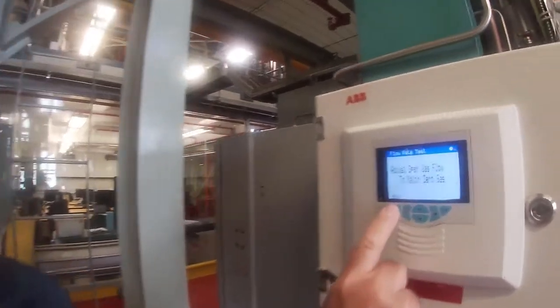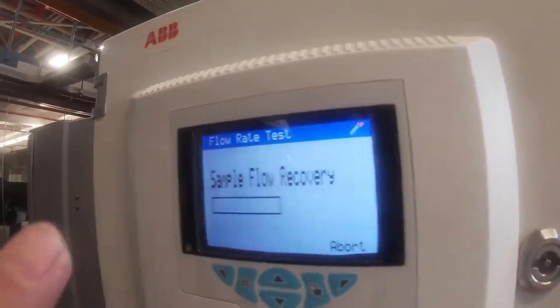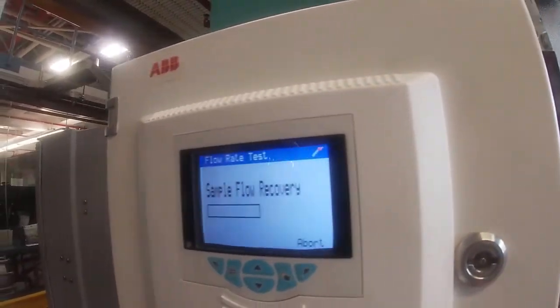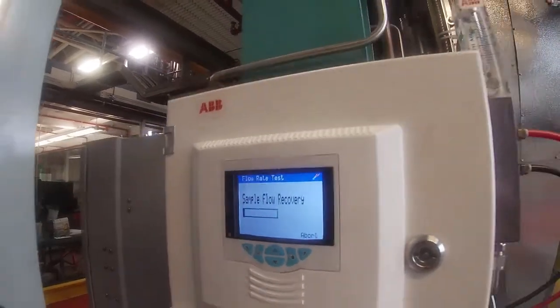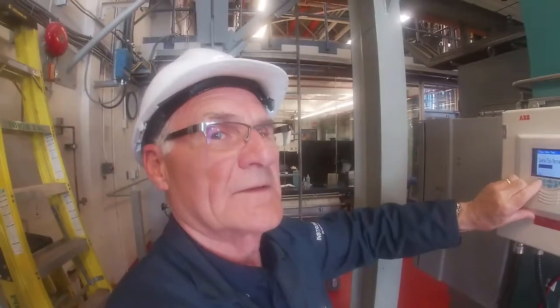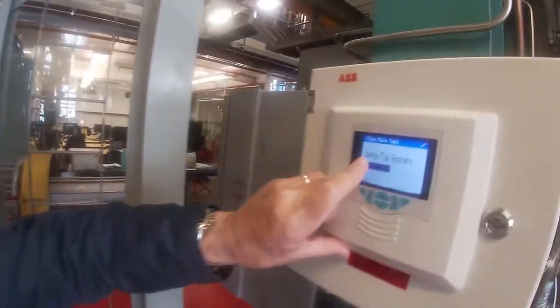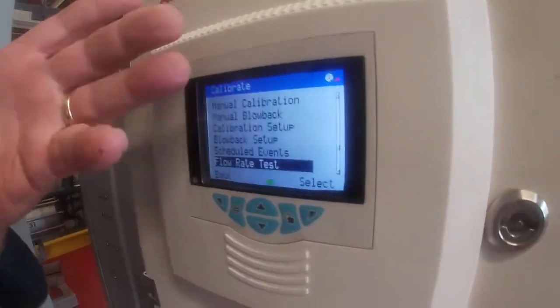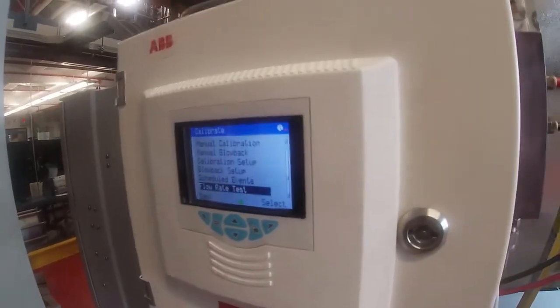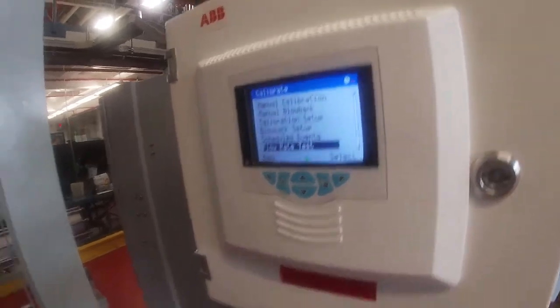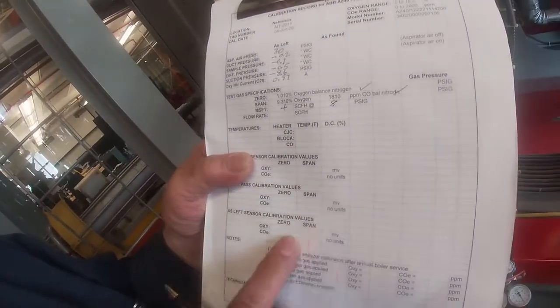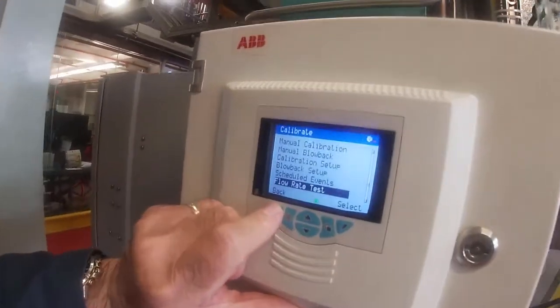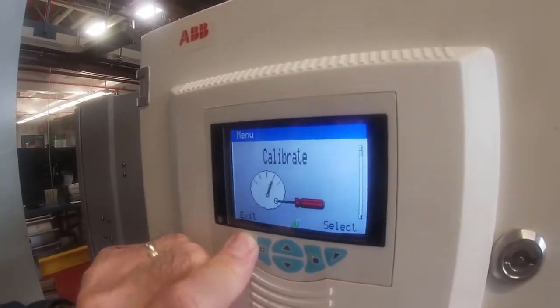Okay, next key. It basically just shut off the gases, and remember we put 60 seconds of recovery time in there, so in 1 minute this is going to say it's recovered. So I'm going to hit the next key to come out of the sample flow recovery, and I'm back to the beginning. Now I'm actually going to move backwards because I need to fill a whole bunch more data in on here before we actually go through and do our calibration. So I'm going to back out, and I'll remember how to get back in here.